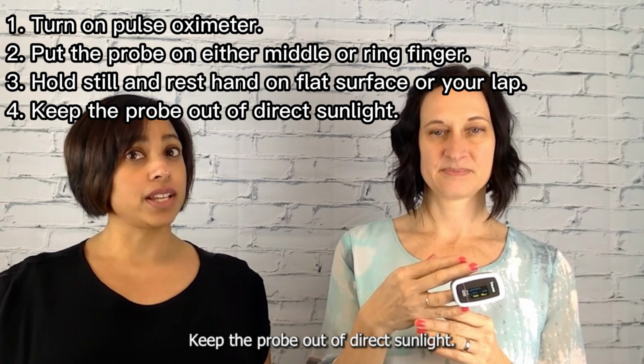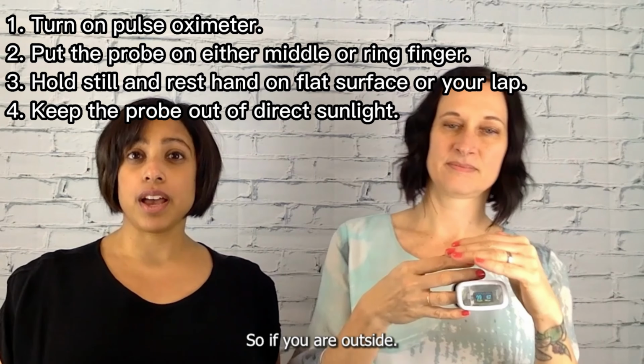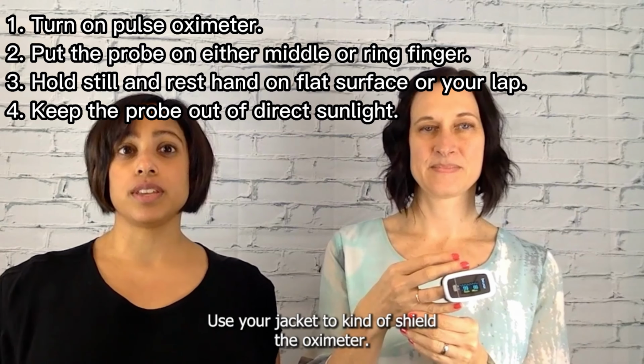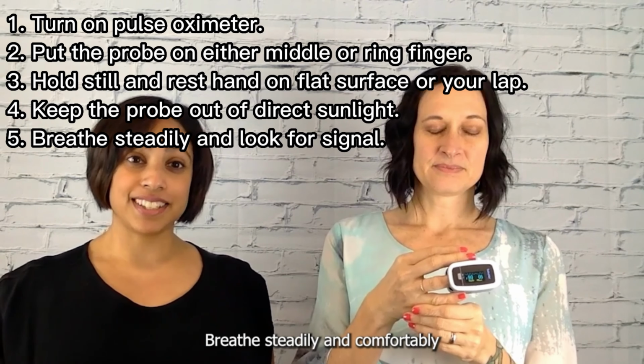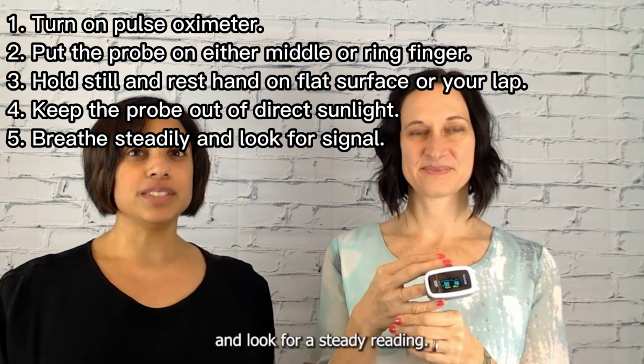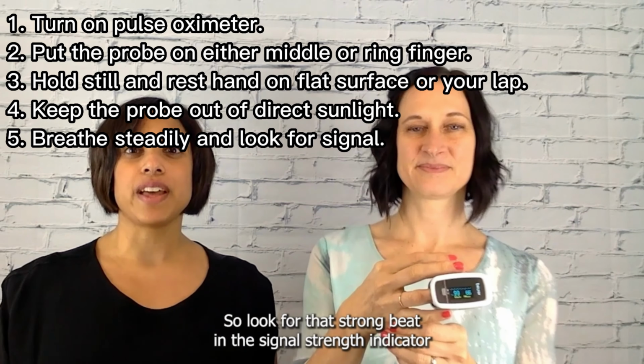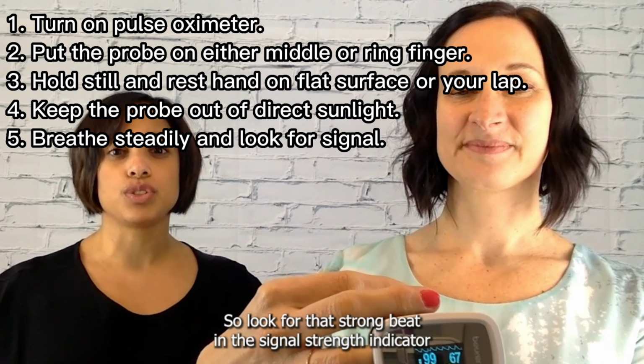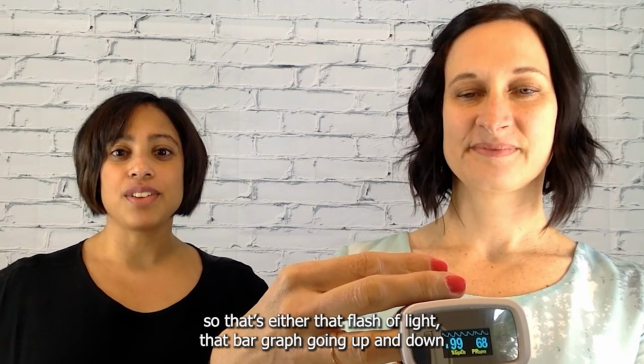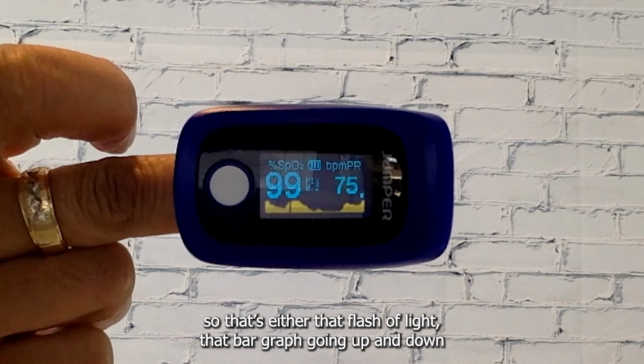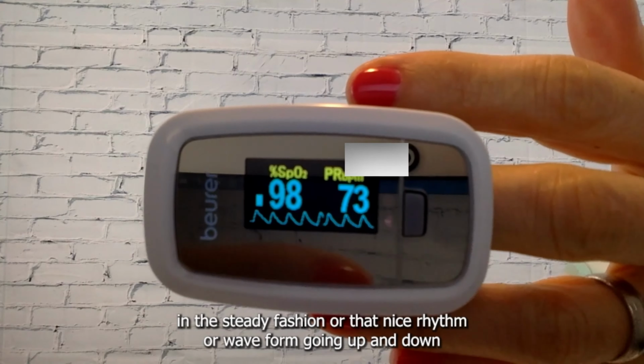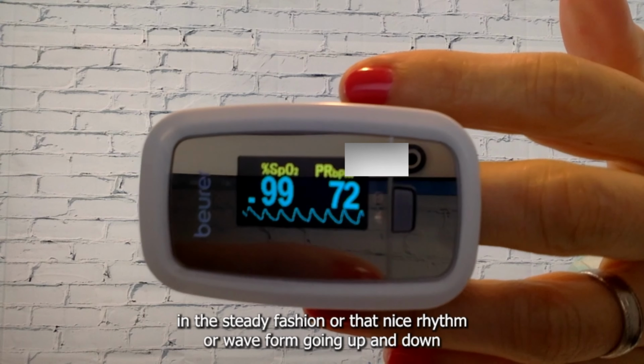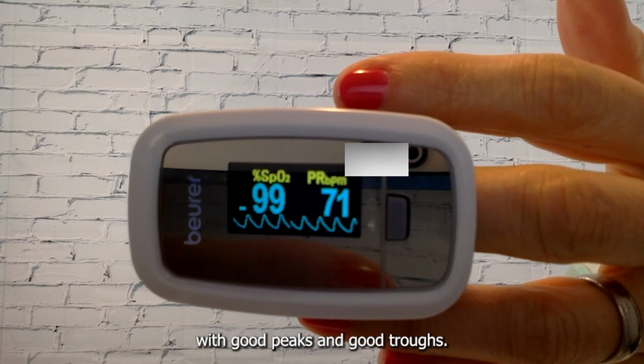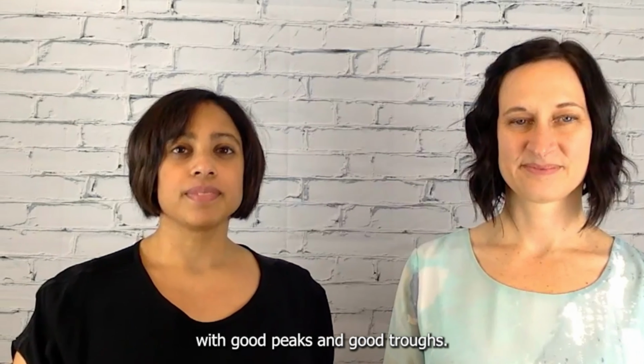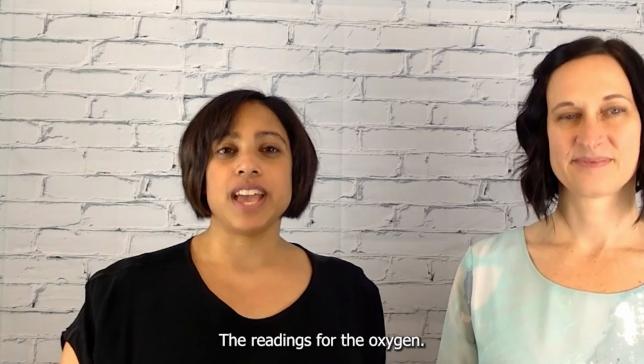Keep the probe out of direct sunlight, so if you're outside, use your jacket to kind of shield the oximeter. Breathe steadily and comfortably, and look for a steady reading. So look for that strong beat in the signal strength indicator. So that's either that flash of light, that bar graph going up and down in a steady fashion, or that nice rhythm or waveform going up and down with good peaks and good troughs. The readings for the oxygen and the heart rate should stabilize.